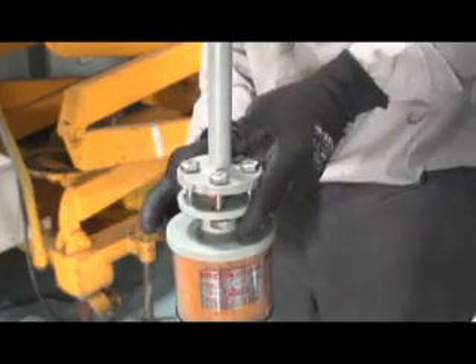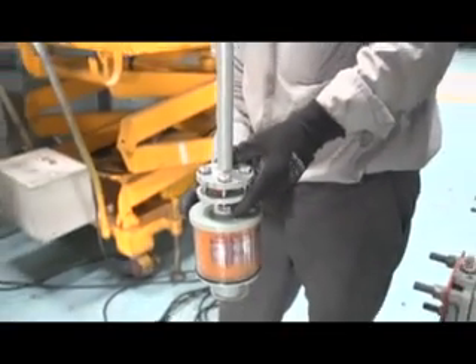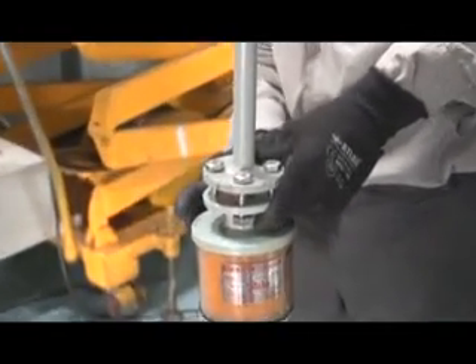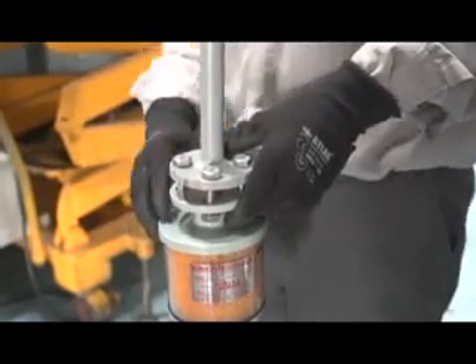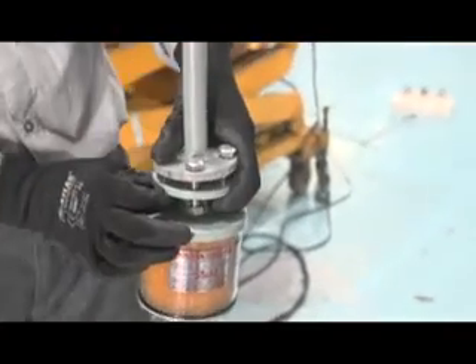When there is sufficient difference between the air inside the conservator and the outside air, the oil level in the two components of the oil seal changes until the lower oil level just reaches the rim of the inverted cup. The air then moves from the high pressure compartment to the low pressure compartment of the oil seal.